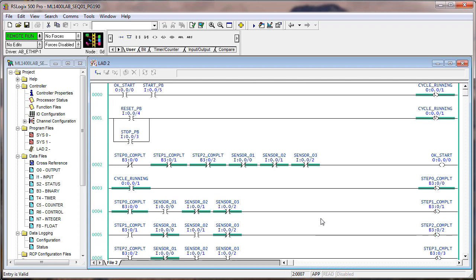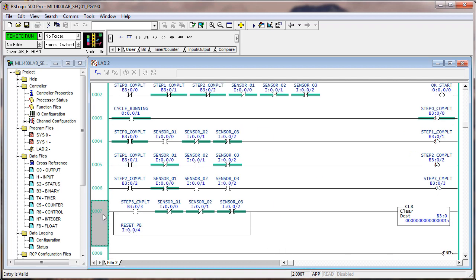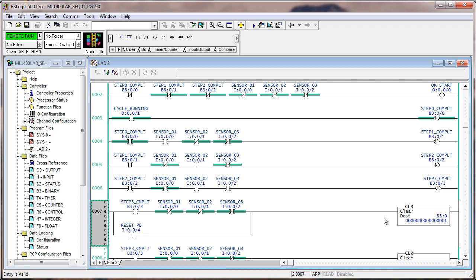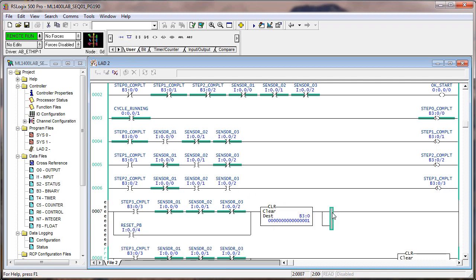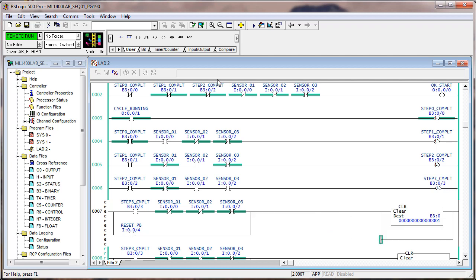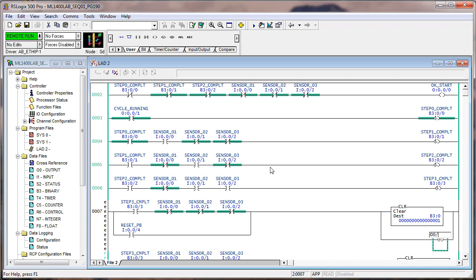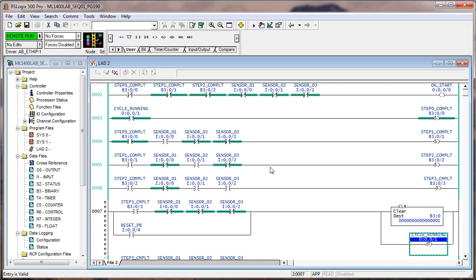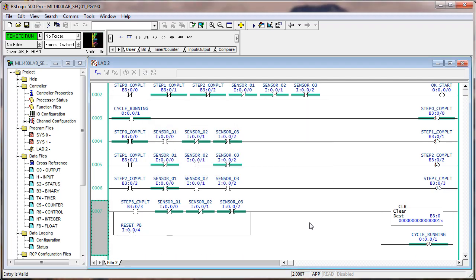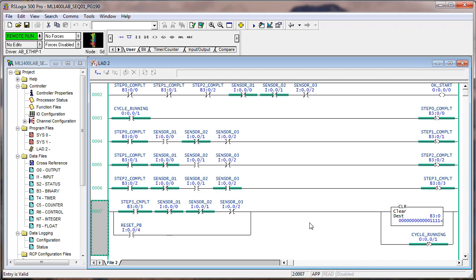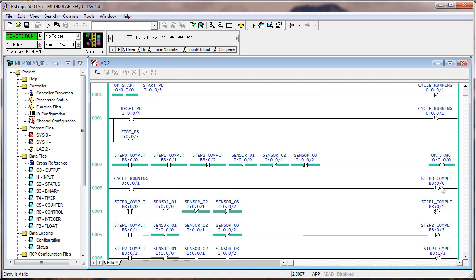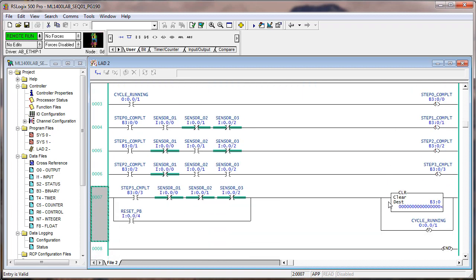If we wanted it to come to a complete stop, then we would have to also unlatch output one. And we could do that simply by putting a branch around. Now we'll step it through again. We do sensor one, sensor two, sensor three. Put them back in the right position. And now we've stopped. Step zero is not already complete like it was before we added this unlatch on cycle running. So you see how you just kind of build your sequence a little bit at a time.